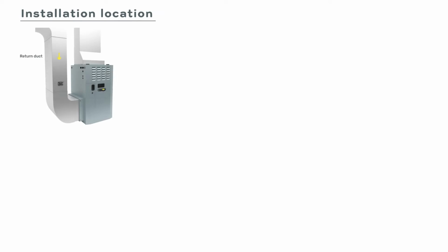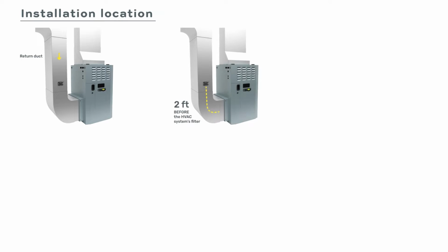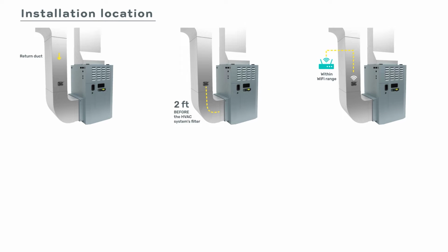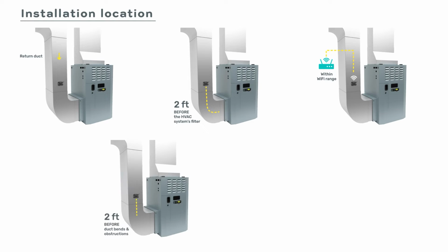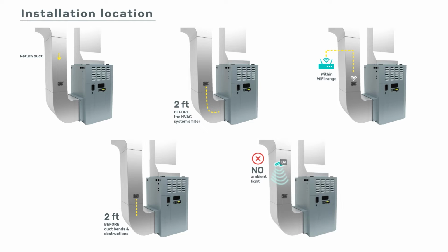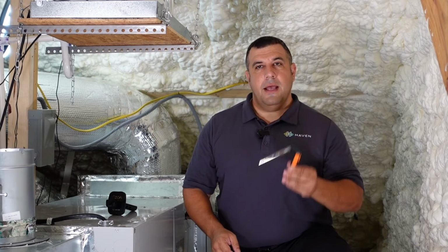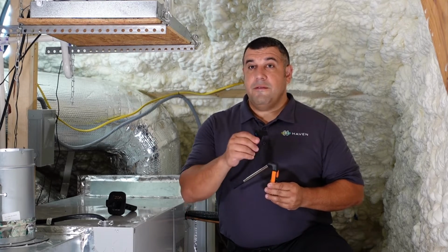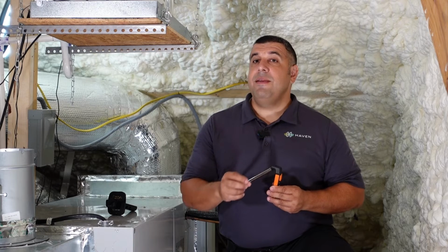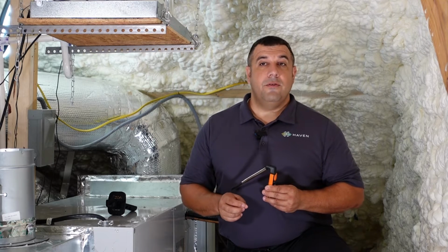You'll need to validate that your installation location is in the return duct at least 2 feet before the filter of the HVAC system, within range of the home's Wi-Fi network, ideally away from duct bends and other obstructions, and not in the same location as any ambient light sources like UV lights. It is recommended to take a reading on your anemometer to ensure that the fan speed is able to reach 80 feet per minute or 0.4 meters per second.